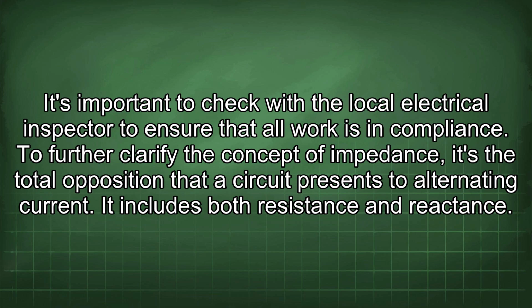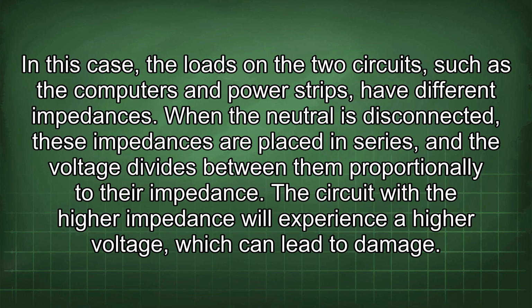To further clarify the concept of impedance, it's the total opposition that a circuit presents to alternating current. It includes both resistance and reactance. In this case, the loads on the two circuits, such as the computers and power strips, have different impedances. When the neutral is disconnected, these impedances are placed in series and the voltage divides between them proportionally to their impedance. The circuit with the higher impedance will experience a higher voltage, which can lead to damage.